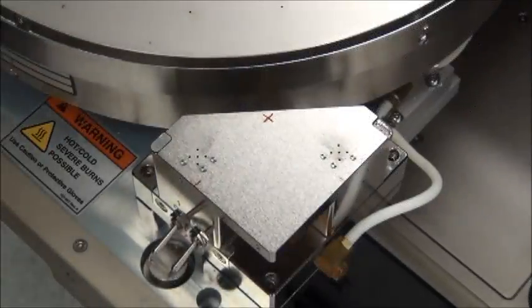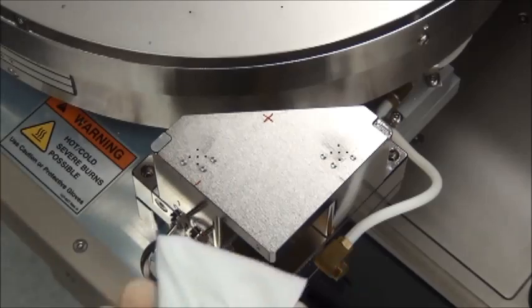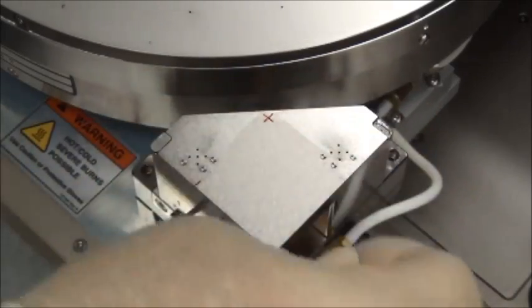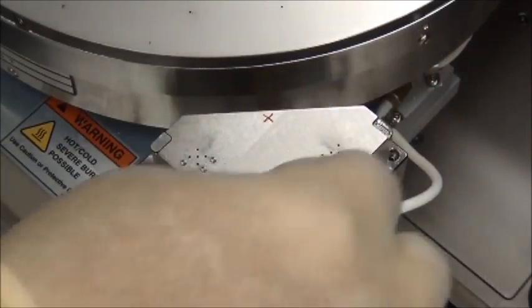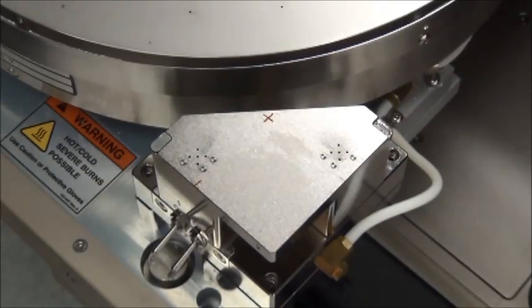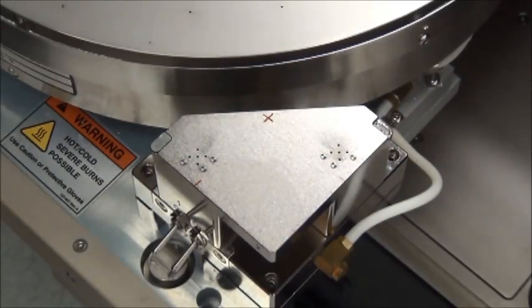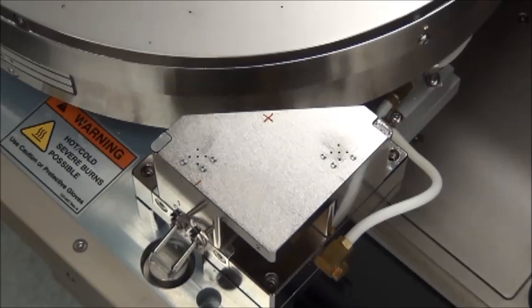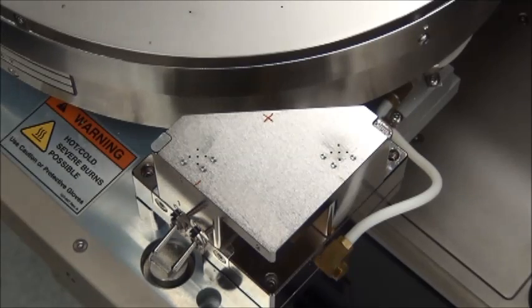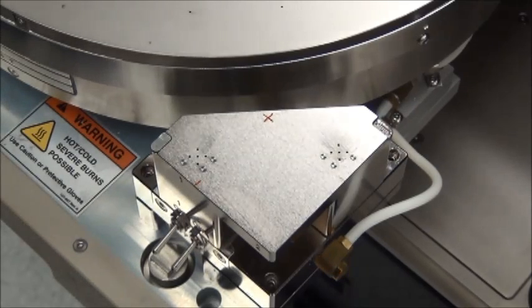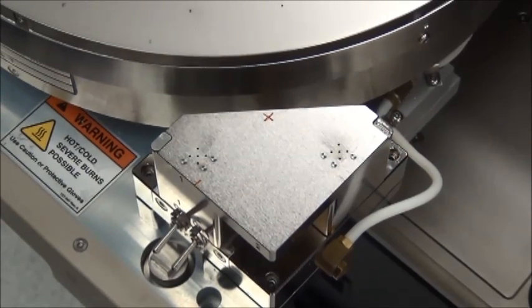Before installing a cleaning pad on the surface of the aux chuck, it is critical to ensure the chuck surface is free from any debris. With gloved hands, use a non-particulating alcohol wipe to clean any foreign debris from the surface of the chuck where you will be securing the cleaning pad. Also visually inspect the surface of the chuck to ensure there are no pits or burrs in the metal surface that may cause probe tip damage if contacted. Allow the alcohol to dry, then get ready to install the cleaning pad.